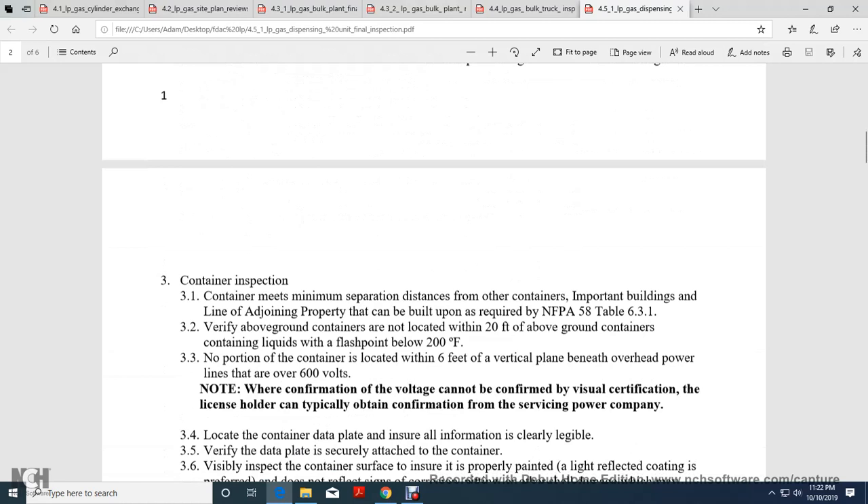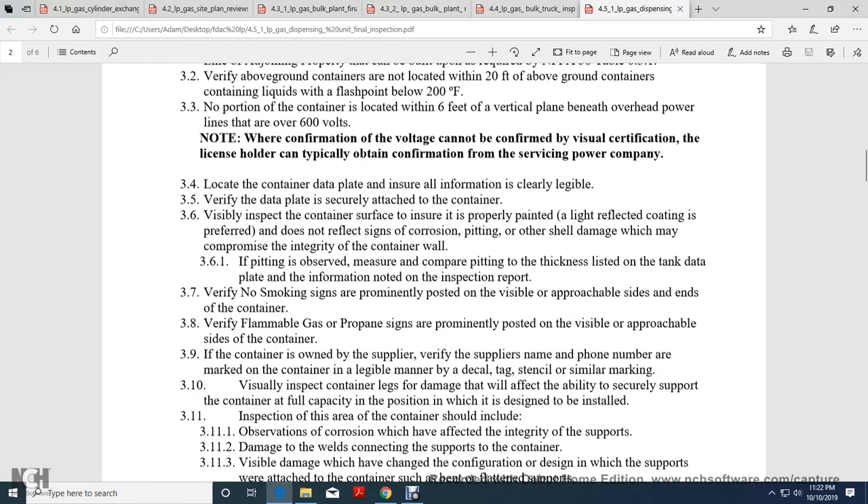Container Inspection: Containers must meet the minimum separation distance from other containers, buildings, and the line of adjoining property that can be built upon, as required by National Fire Protection Association 58-6-3-1 table. Verify above-ground containers are not located within 20 feet of containers containing liquid with a flashpoint below 200 degrees. No portion of the container shall be located within 6 feet of the vertical plane beneath overhead power lines of 600 volts. Note: when voltage cannot be confirmed by visual certification, the license holder must obtain confirmation from the power company.